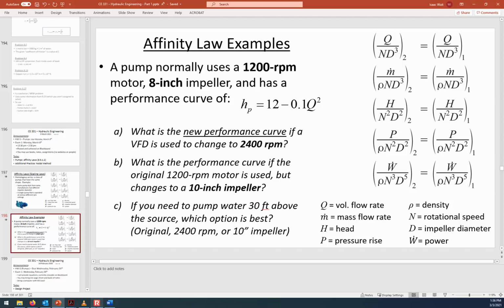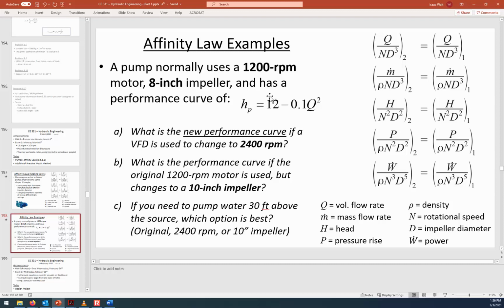This part C is not really a calculation question. What it's asking you to do is remember what the intercept of a pump performance curve means. Our original pump performance curve has an intercept of 12 feet, meaning the maximum head that pump can add is 12 feet. If we need to lift water 30 feet, 12 feet of cutoff head isn't enough. You'd turn on the pump and it would spin, but it wouldn't give enough energy to lift the water.